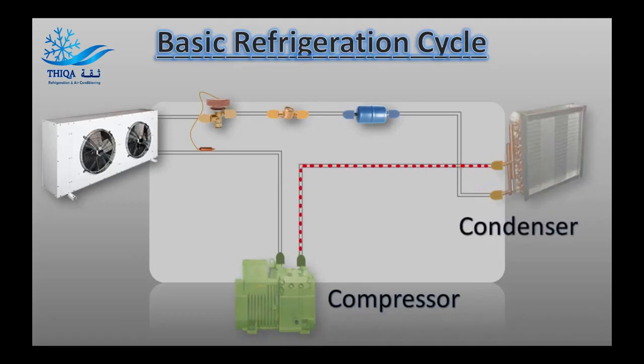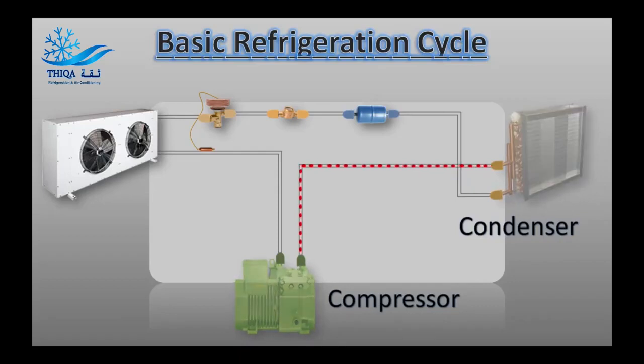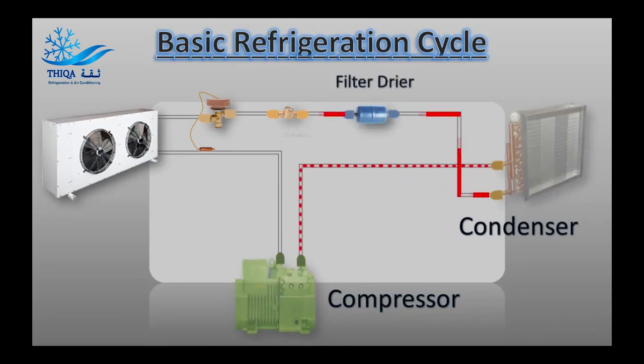Second, the condenser. The condenser, or condenser coil, is one of two types of heat exchangers used in a basic refrigeration loop. This component is supplied with high-temperature, high-pressure vaporized refrigerant coming off the compressor. The condenser removes heat from the hot refrigerant vapor until it condenses into a saturated liquid state, aka condensation.